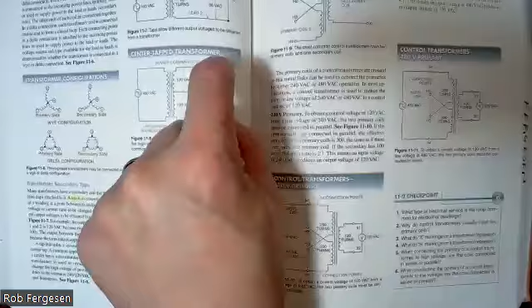The most important purpose of going through transformers in this course is talking about control transformers, used to step up or step down the voltage. Generally speaking, I might have three-phase power at, say, 208 or 480 or 460. When I hook up my giant machine, I don't want to have to run a whole different group of wires down to that machine. I just want to run three big fat wires to bring down three-phase to that machine.